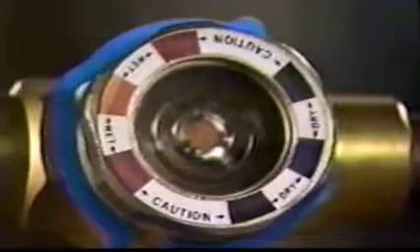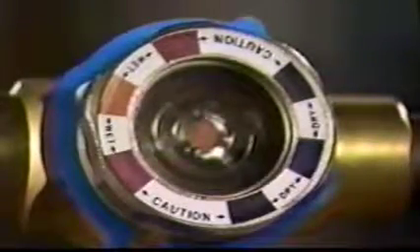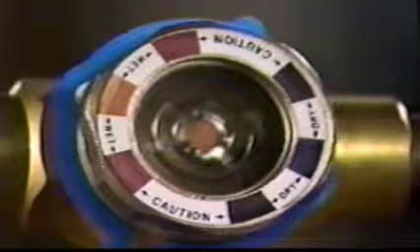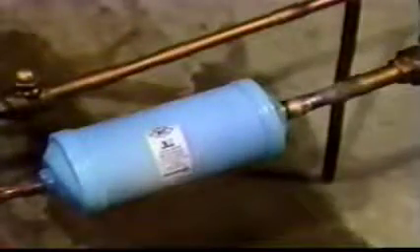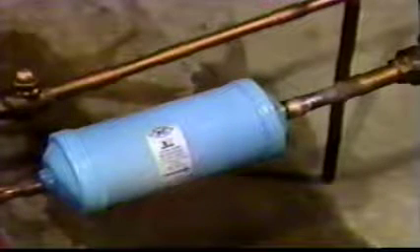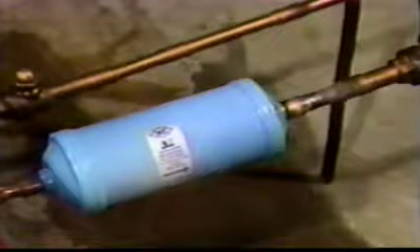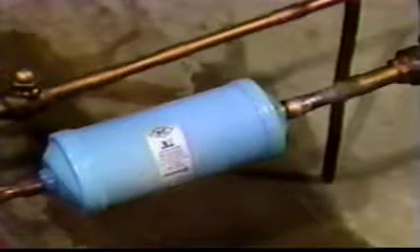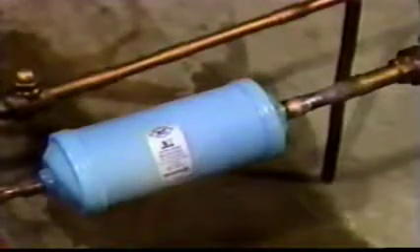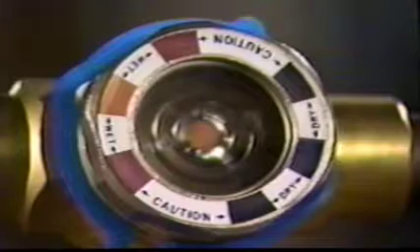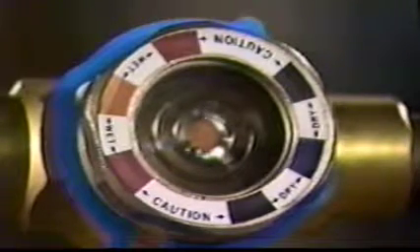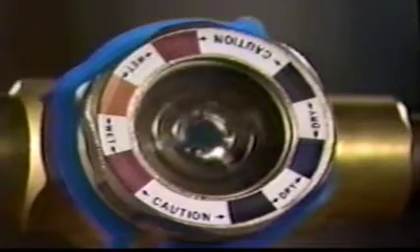If the liquid line filter dryer is not being used as a burnout cleaner, it will be high moisture that determines when it's time to change to a new dryer. The bigger is better rule will apply to a filter dryer where moisture content may be extremely high. Since moisture is best removed at the liquid line location, it may be necessary to use an oversized filter dryer to handle an excessive amount of moisture that may have entered the system. If, even after the installation of an oversized dryer, there is still an indication of excessive moisture, the filter dryer must be replaced until the technician is convinced the system is dry.